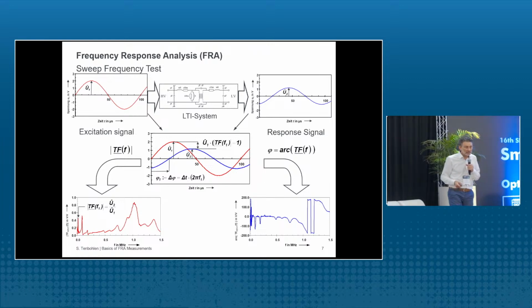And for the frequency response analysis, we evaluate this frequency spectrum here. Because if you have a mechanical deformation, the capacitances in the winding are changed. And if you change the capacitances, of course also the resonance frequencies of these windings are shifted. Yeah? So you can see here, for example, a resonance frequency at 1 megahertz, and if you change the capacitances within the winding, this resonance is shifted to lower or to higher frequencies. And once you detect such a shift of frequencies, then you can say there's a problem inside the transformer.